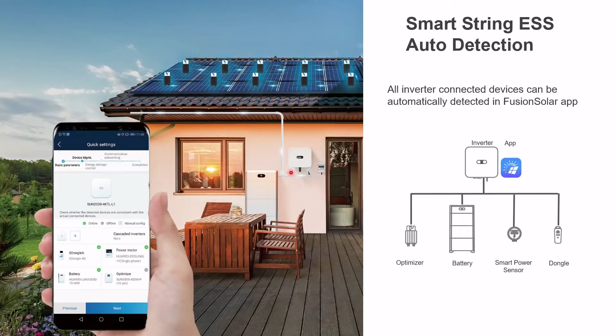Until the sun starts and our PV starts, we use energy from the grid. Then the output power of the inverter is shown in this gray field. This is the power produced at the output, but all the excess power goes to the battery from the DC to DC side until the battery is fully charged—this is the only situation when power is exported to the grid.